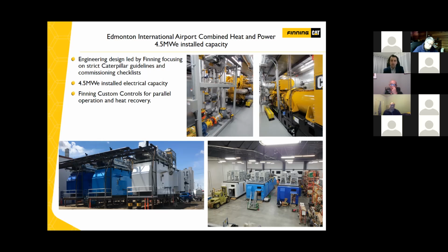As Jim was saying, in case you want to run in electrical mode only, or in case you're running in summer months and don't require the heat, you have a heat dump radiator, in this case right on the rooftop. Next to it on the rooftop is also a heat exchanger. The jacket water heat exchanger is inside these enclosures, right in front of the engine. And as Jim pointed out, it's not very large—they're surprisingly small for what they do.